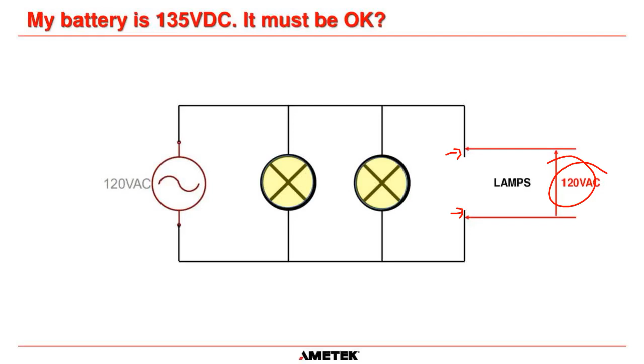The same applies to a battery. Instead of 120 volts AC going to a house, we have a charger coming in, and let's say we have 3 strings of batteries that all measure 135 volts DC, exactly like the AC example. If we removed one battery completely and measured the potential at the lugs going to the battery we lifted, we'd still read 135 volts DC because they're in parallel.